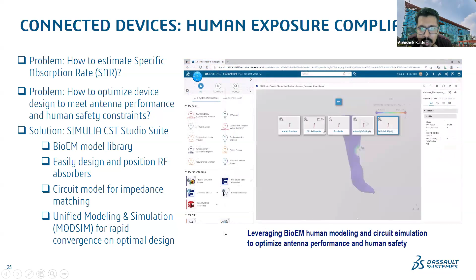Nivedita will cover this in detail later on. In this case, it's a hand model. And what we do here is we place the device on it, and we try to see what exposure is absorbed into this human tissue. So in this case, you can see that the SAR rating mentioned over there is about 4.2 watt per kg. That's too high. The limit specified by the FDA standard is 1.6 watt per kg, which means this can pose a threat. So what we do is we insert this absorber. This is an RF absorber which absorbs a lot of your RF energy, or radio frequency energy, and then you see what the performance is.